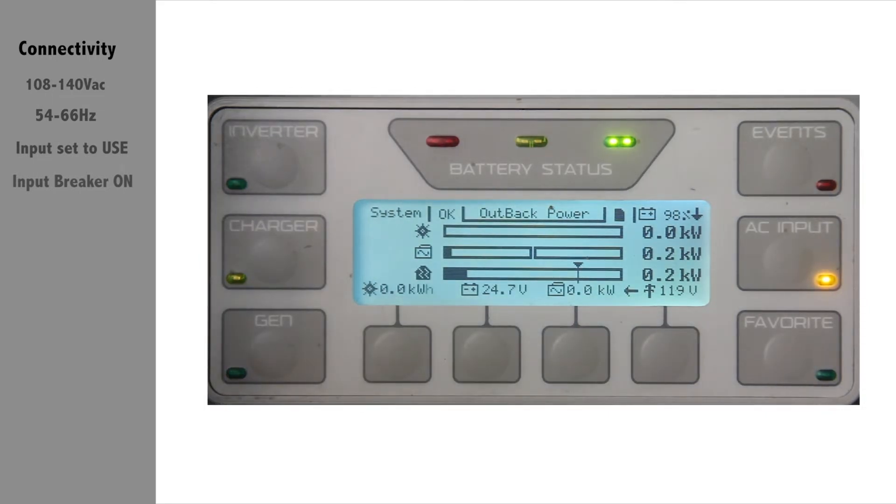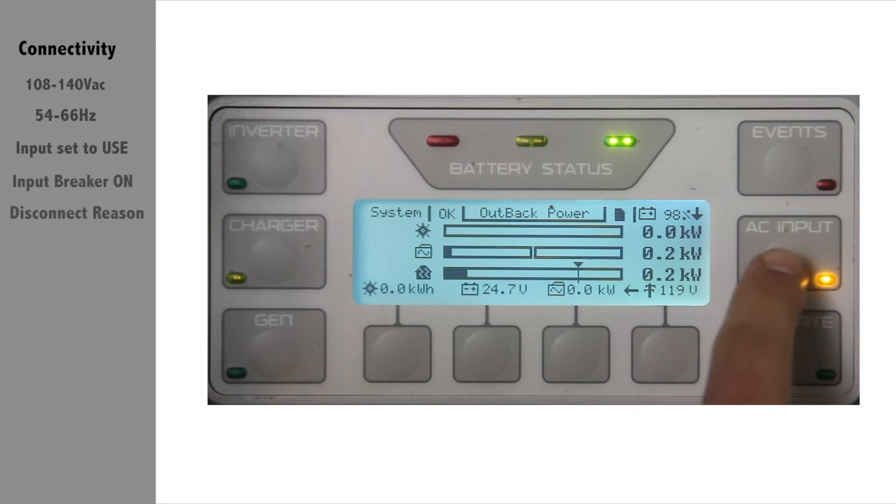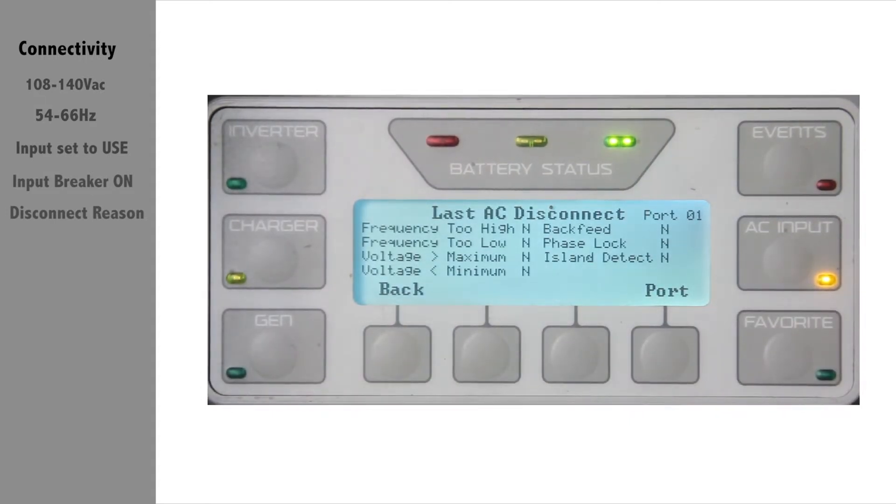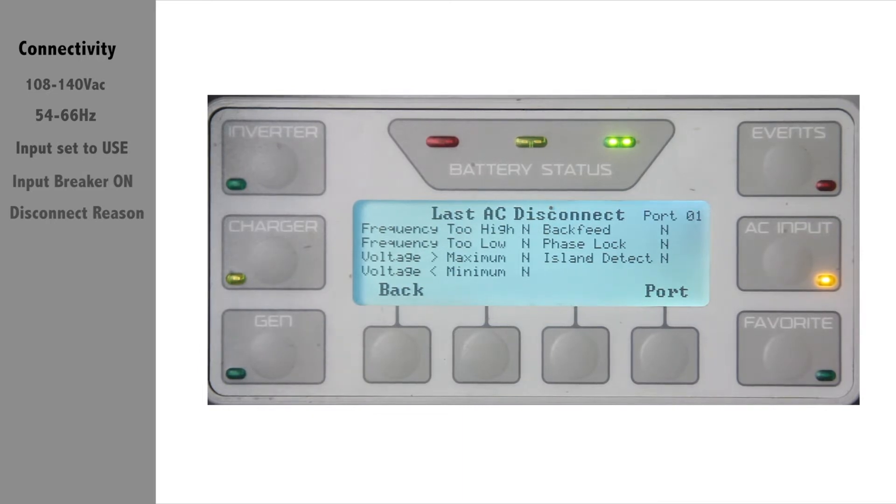If this is the case, you can find out why the inverter rejected generator power by going to the Mate 3, then press the AC input hotkey, then press on disconnect. Here it will show you the last AC disconnect reason.